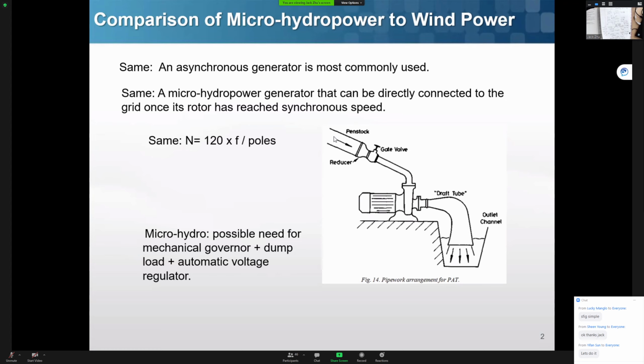Because you always will have water flow down there, and we know the load connects onto the generator. Any generator, if you don't control the speed or the input power, when the load varies, let's say you might have a 5 kilowatt generator down there, if you're only demanding 1 kilowatt of electrical power, or you're demanding the full 5 kilowatts, when the generator takes on more load, you will for sure try to slow the generator down.